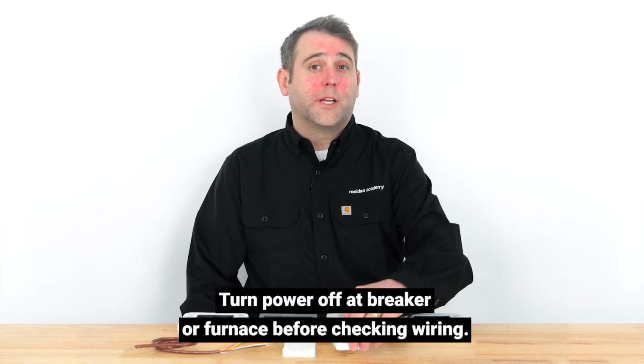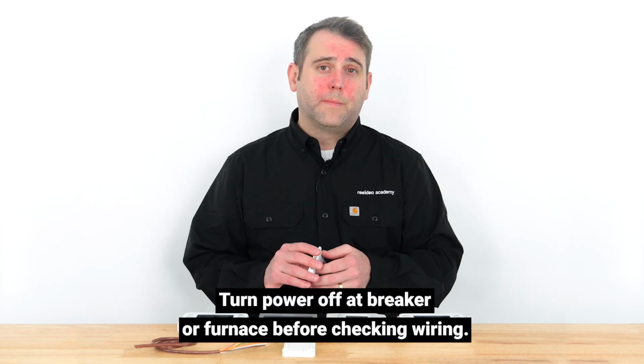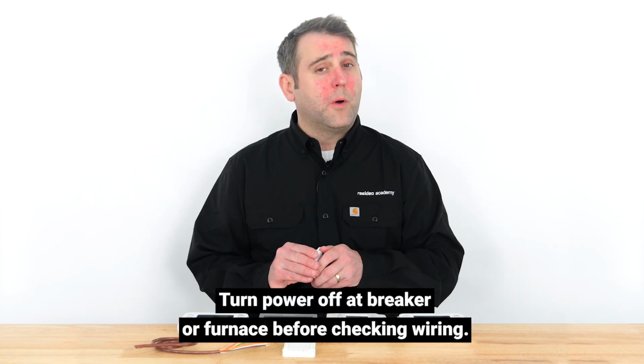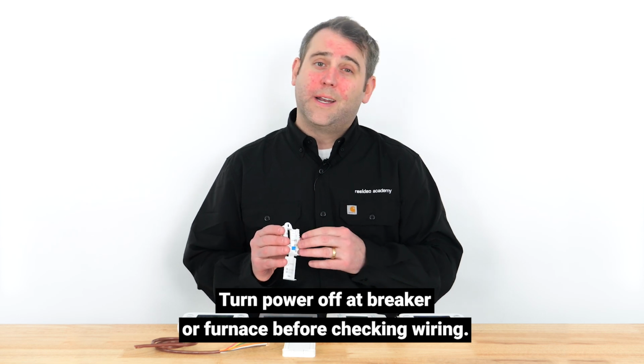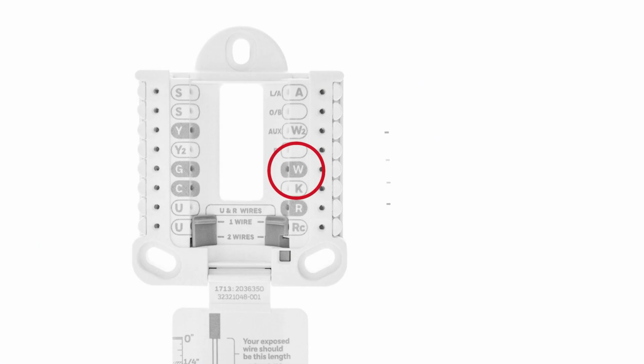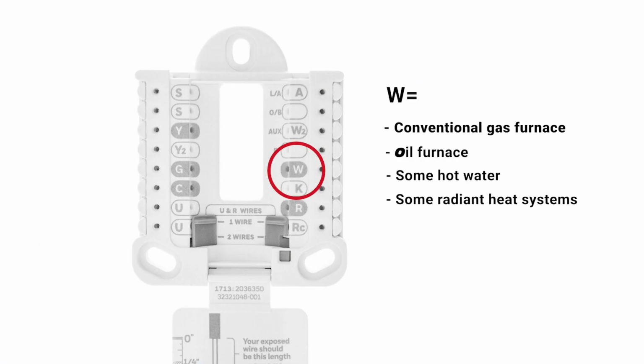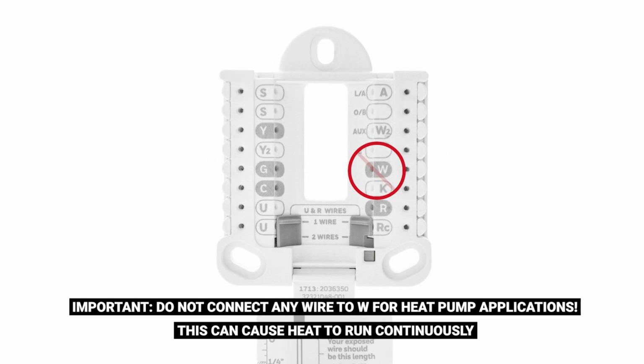If compressor protection isn't the issue, check the wiring based on your system type. Confirm all your wires are in the correct terminals and have good contact. For heating, the W terminal controls the heat for a conventional gas or oil furnace and for some hot water or radiant heat systems. If you have a heat pump system, you will not connect any wire to the W terminal. This can cause heat to run continuously.